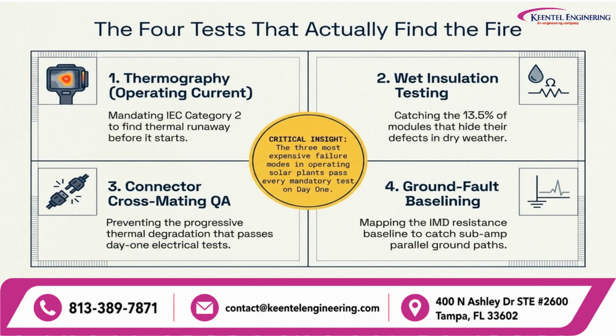To genuinely safeguard utility-scale assets against failure and fire, 4 critical testing protocols must be elevated from optional recommendations to non-negotiable requirements. First, full load thermography under true operating current to expose thermal runaway early. Second, wet insulation testing to catch the critical percentage of dielectric faults invisible in dry conditions. Third, connector cross-mating quality assurance to eliminate dimensional interface mismatches. And fourth, active ground fault baselining to establish insulation resistance references before sub-amp leakage paths cause nuisance inverter tripping.